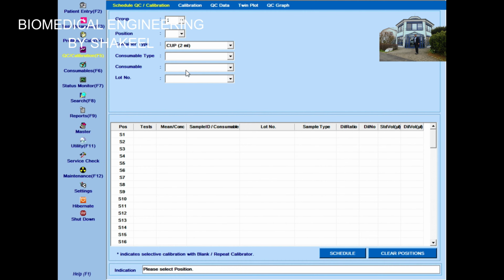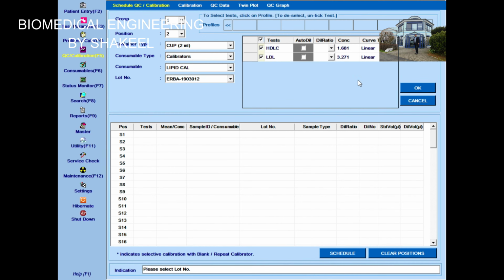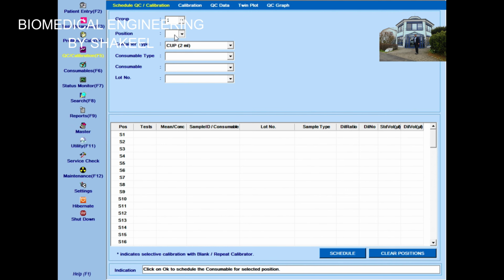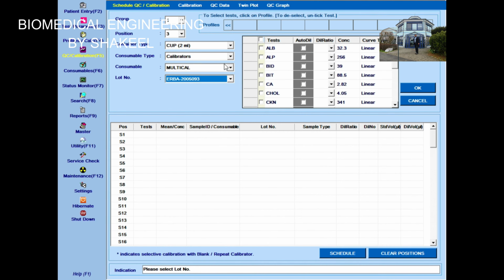Now let me select the calibrator. So I'm going to select the lipid calibrator for the lipid calibration. So you can see that I have selected lipid cal for HDL and LDL. And now I'm going to select the calibrator for the other parameters. So I'm going to use the multi-calibrator. So click on multi-calibrator. So here I will select the test which I already selected for the calibration purpose.